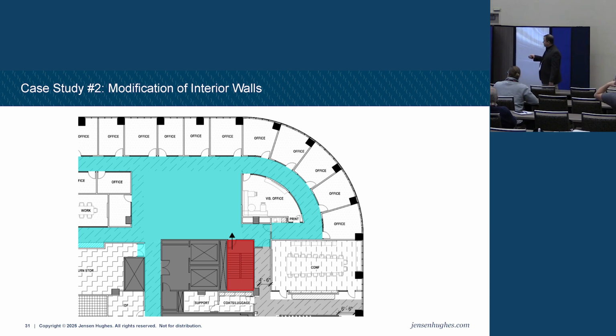So now I put the system into alarm, and I have to measure differential pressure from here to here and here to here. So these 2 spaces and these 2 spaces. So the red and green and the green to gray. Now I do this, I guarantee you my fans can't do that anymore, right? So I just changed the volume I have to provide pressurization for.